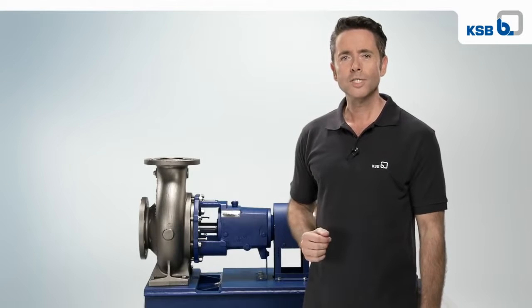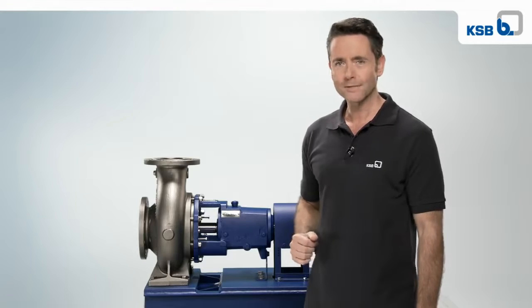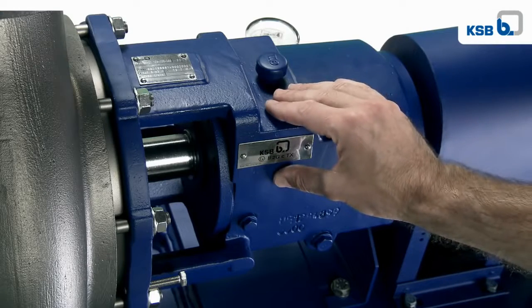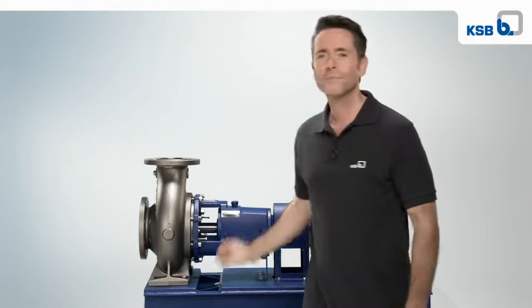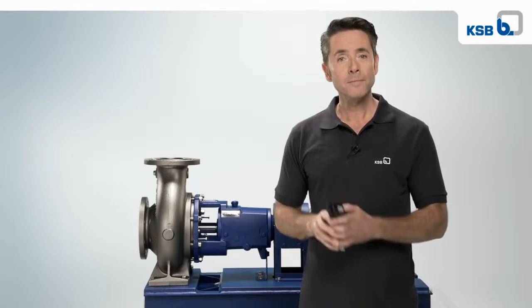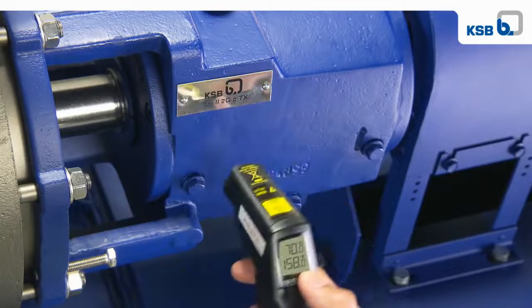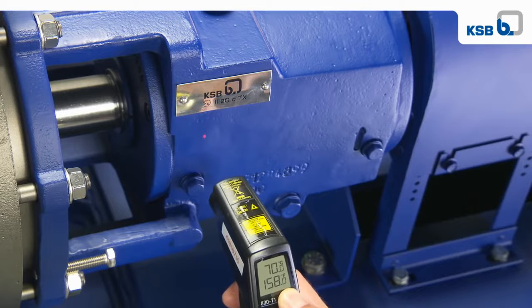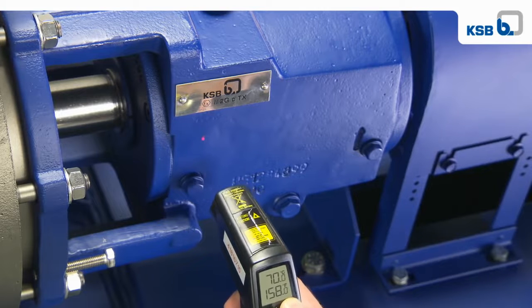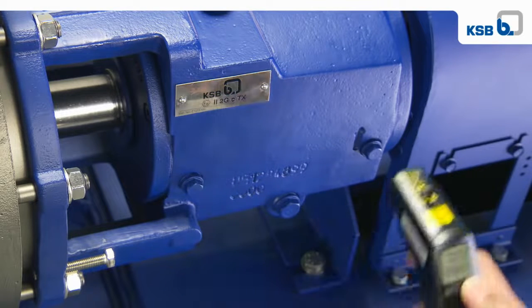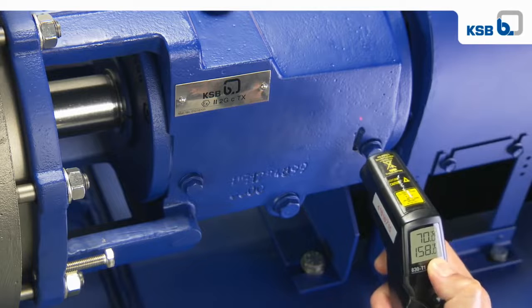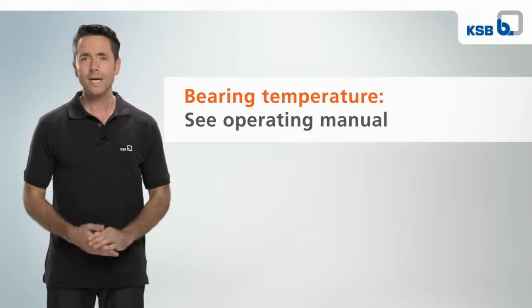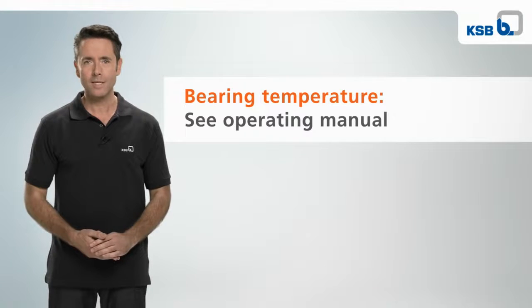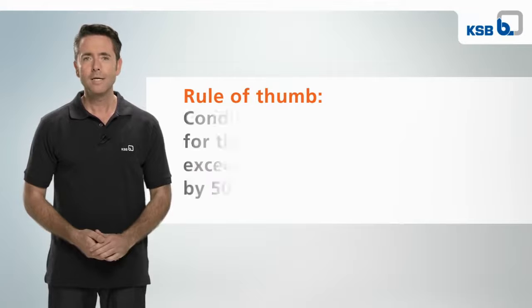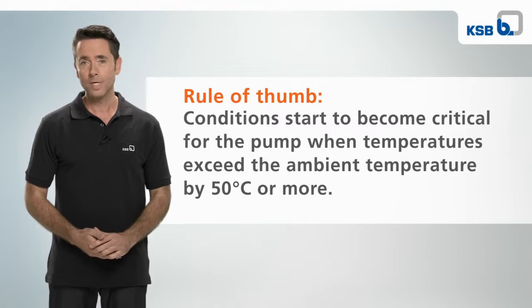You can determine whether the bearing temperatures are higher than they should be by using your hand, or a measuring gun if the surface is too hot. The cause of elevated bearing temperatures can be related to overload conditions, for instance the operating mode, or misalignment. The permissible bearing temperature is given in the operating manual. As a rule of thumb, things get tricky at 50 degrees Celsius above room temperature.